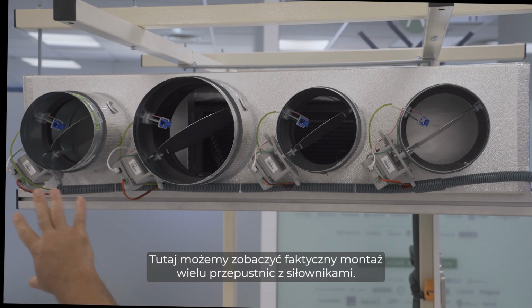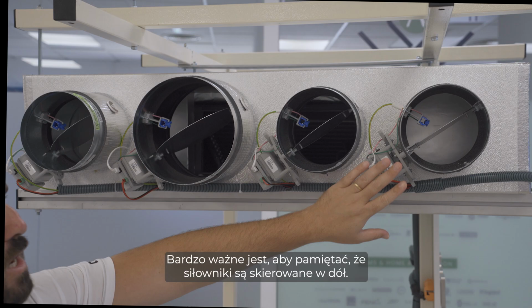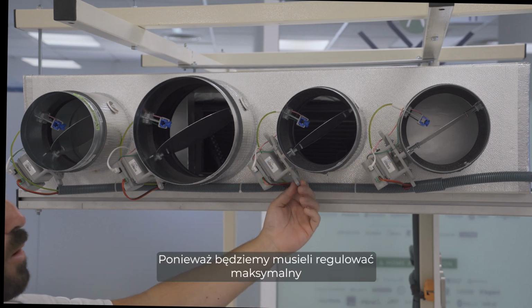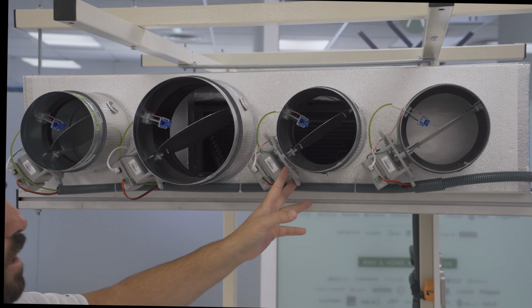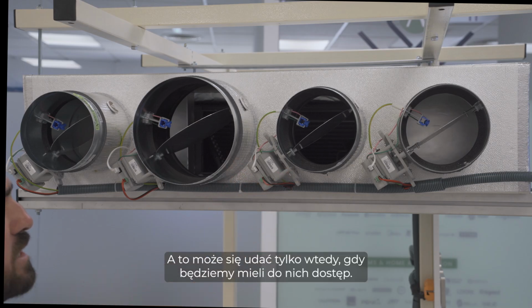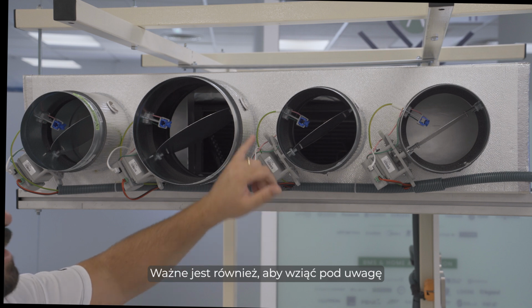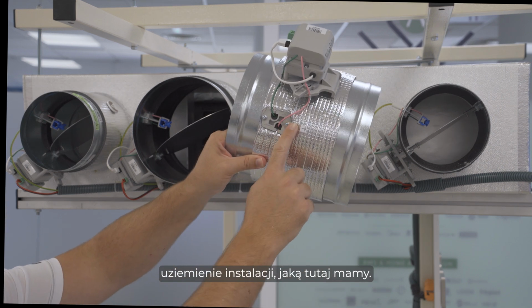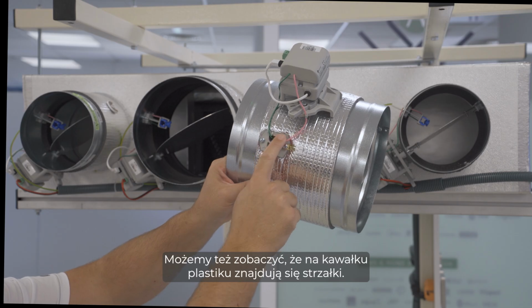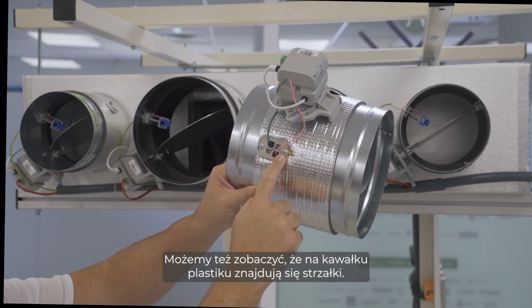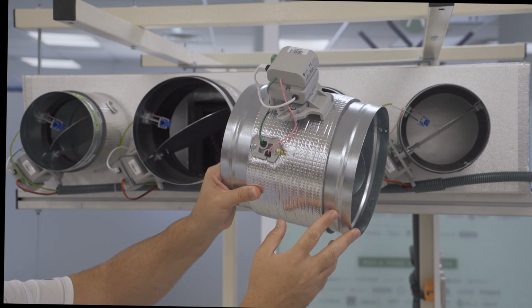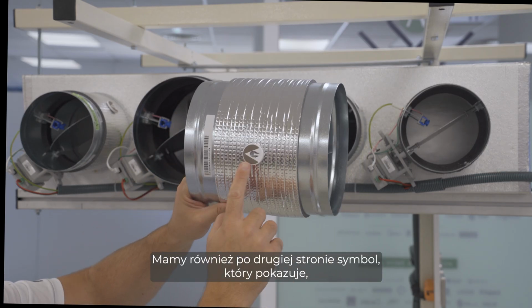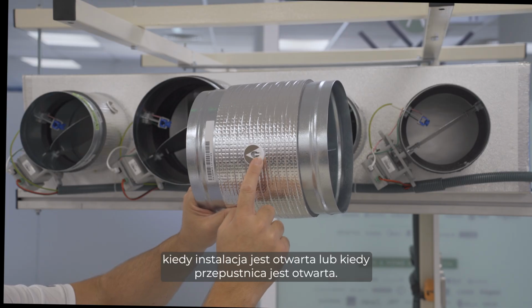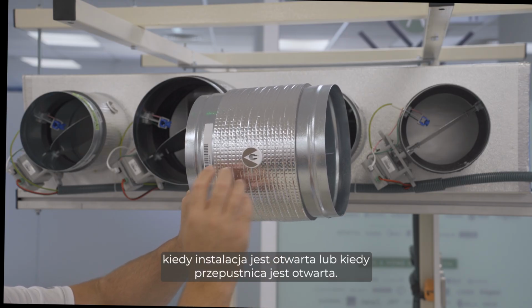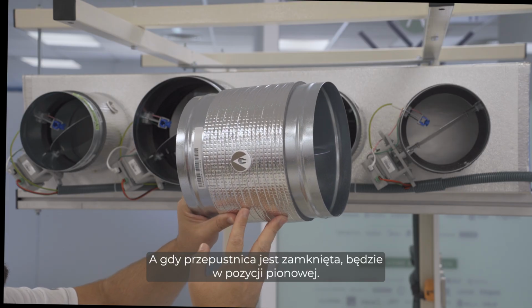So here we can see the actual installation of multiple motorized dampers. It's very important to consider that the motors are facing downwards, okay, because we will need to regulate the maximum and minimum airflow, and that can only be done if we have access to them. Also, it's important to consider the earthing of the installation. We can also see that there are arrows on the piece of plastic, which show the direction of the airflow. On the other side, we have a symbol that shows when the damper is open, and when the damper is closed, it would be in a vertical position.